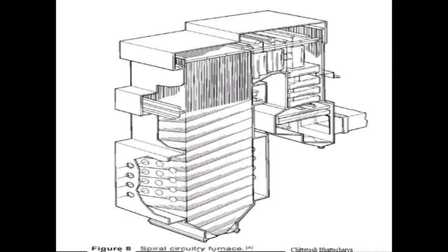In certain water wall systems, we can find spiral tubing. That means the tubings are not vertical, and particularly in supercritical boilers, this spiral tubing arrangement is there so that there is a high speed flow within the tubing with higher heat absorption rate.